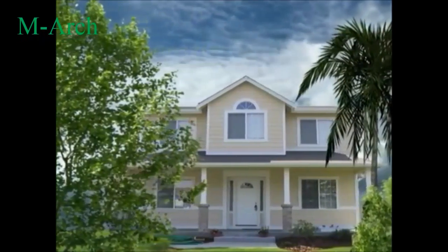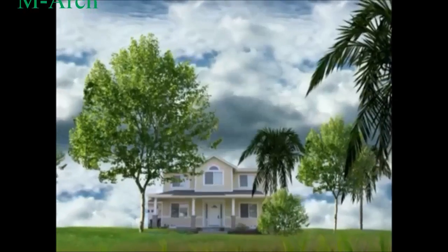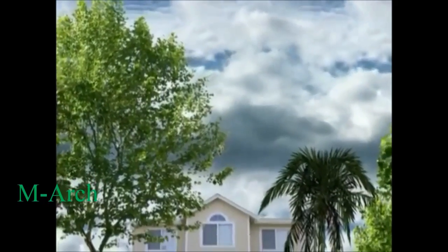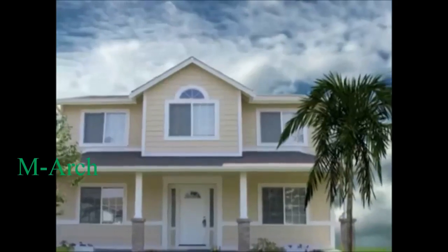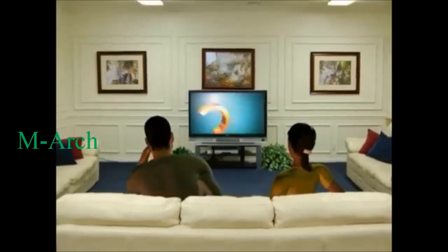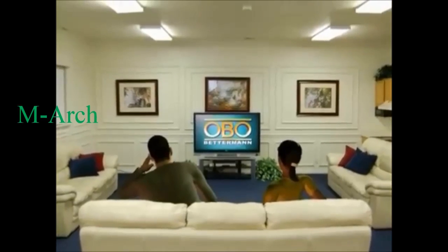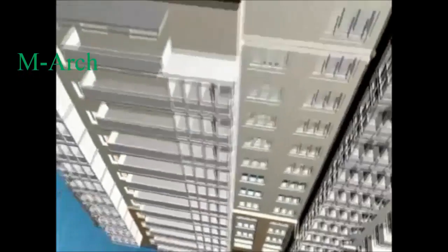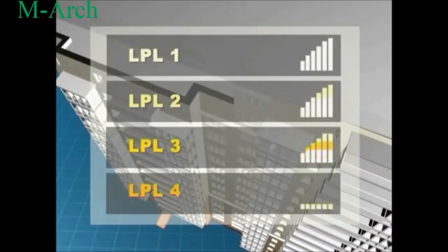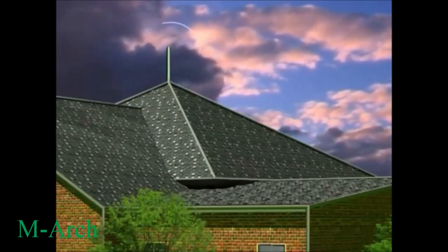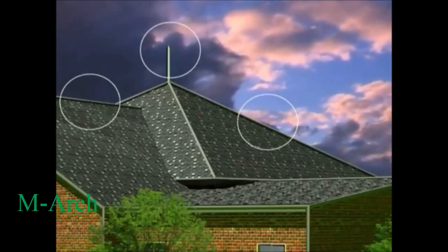Before employing a lightning conductor, the prospective buildings and geographical areas need to be carefully surveyed for the number of times the area is struck by lightning, the trees and tall structures near the building, the area of the building, the number of people living or being employed in the building, and the value of electronic appliances inside the building. The IEC recommends 4 levels of protection based on the factors listed before, from the high-level LPL1 to the normal LPL4 level.